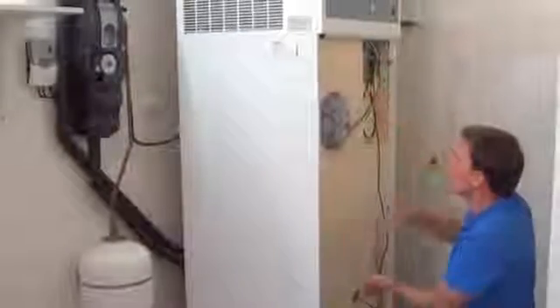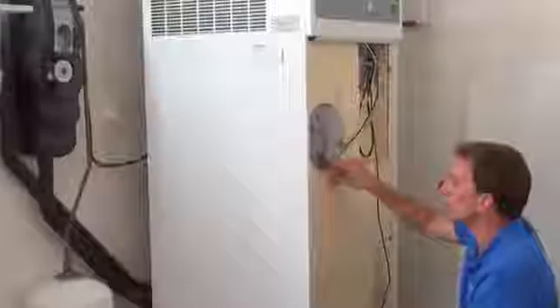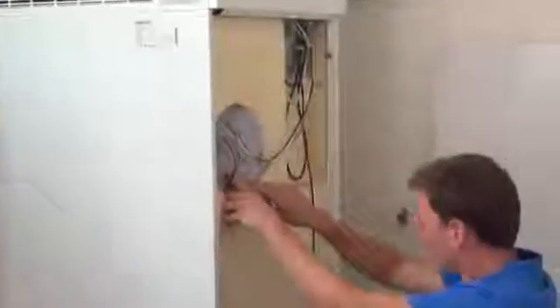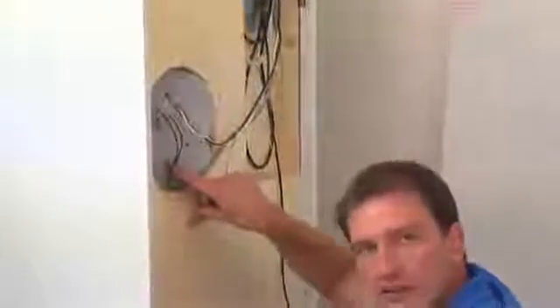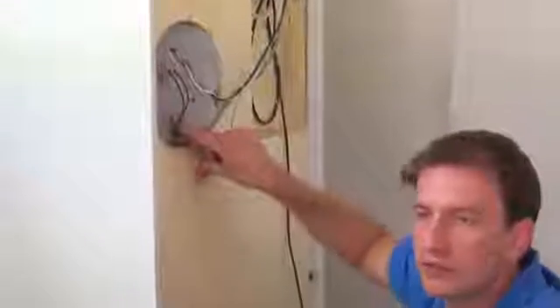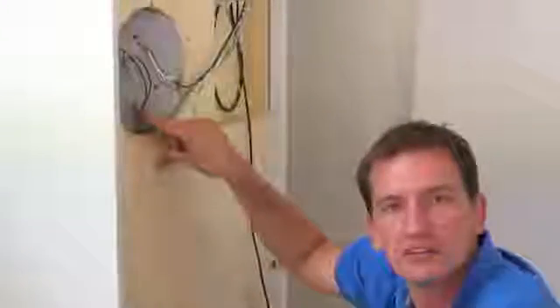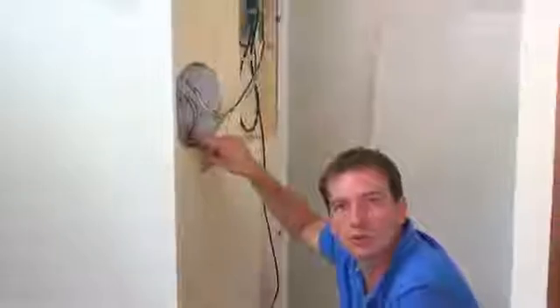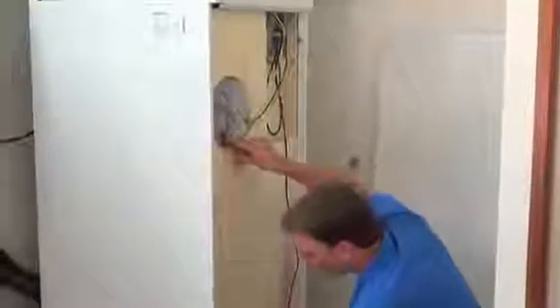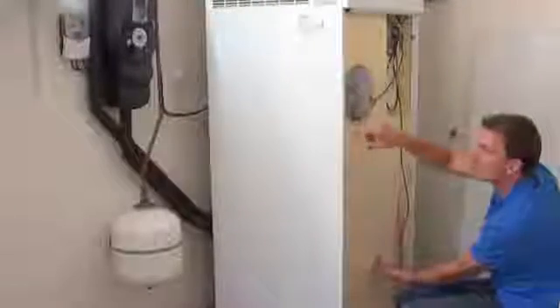When it gets up to the top here, you can see the heat pump sensor, which is a lot higher up on the tank. The heat pump sensor will kick in if you don't have any sunshine. Now, to give a different example, if you don't have any sunshine on a day when you've got overcast weather, or even at night, if cold water comes in the bottom, that will go past the sensor. The computer will not switch on, so the hot water will continue further up in the tank till it gets up to the heat pump sensor. Then only will the heat pump contribute energy.